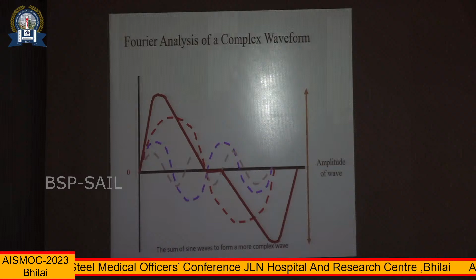The summation of these waves will produce a characteristic arterial trace. Like I said, the frequency at which the stone is dropped, when the first wave is formed, is the first harmonic. You can get up to 25 to 30 harmonics, but the main information is in the first 8 to 10 harmonics, and that is what the monitoring system does. The second aspect is that every system has its own frequency. One is the frequency at which the stone is dropped, plus there is the frequency of the monitoring system. The monitoring system's frequency has to be way higher than the frequency at which the stone is dropped for it to measure reliably and not cause an error. Got it? Okay.